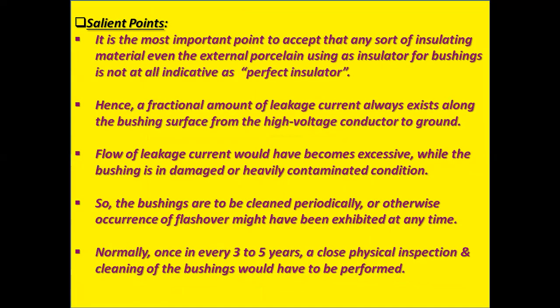Salient points to be noted. It is the most important point to accept that any sort of insulating material, even the external porcelain used as insulator for bushings, is not at all a perfect insulator. Hence, a fractional amount of leakage current always exists along the bushing surface from the high voltage conductor to ground. Flow of leakage current becomes excessive while the bushing is in damaged or heavily contaminated condition. So, the bushings are to be cleaned periodically, or otherwise a flashover might occur at any time.